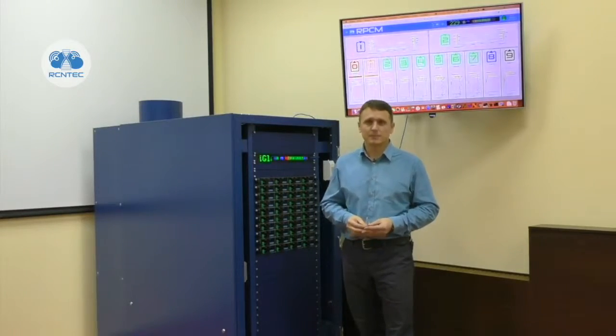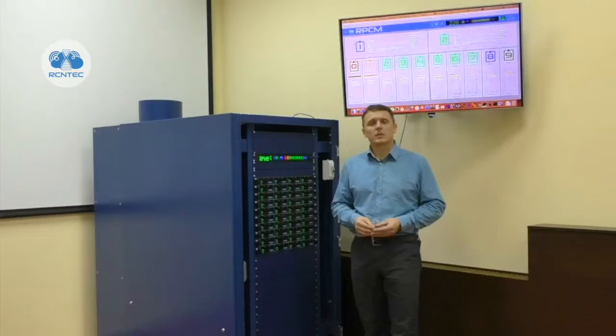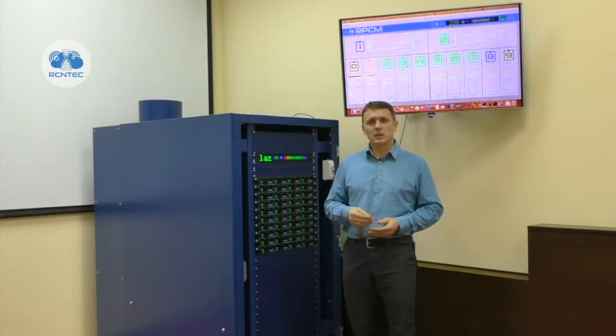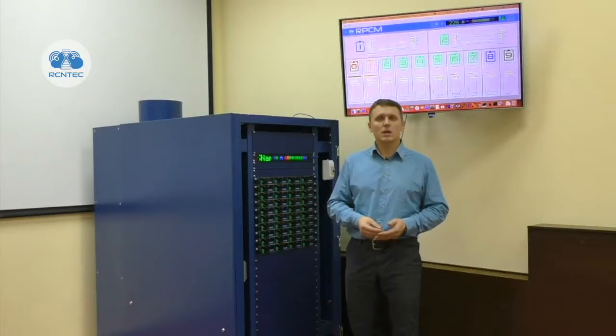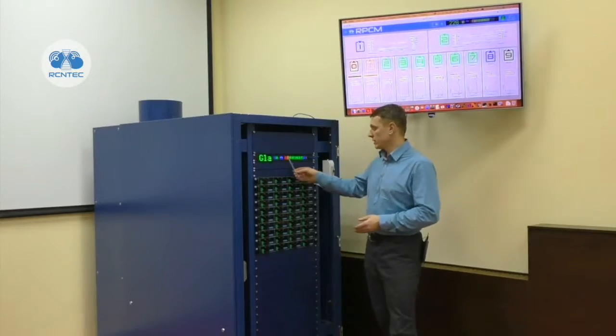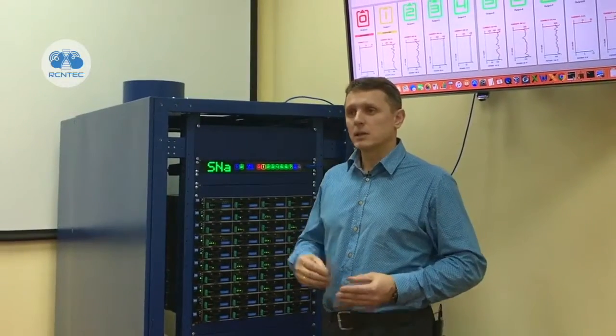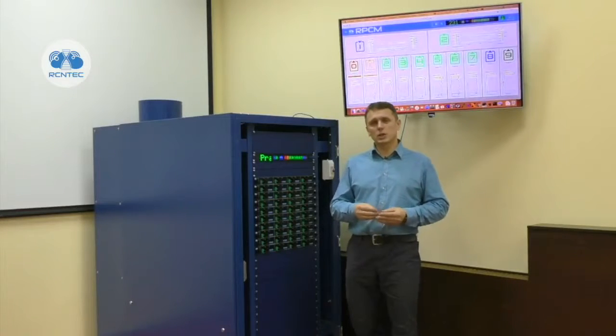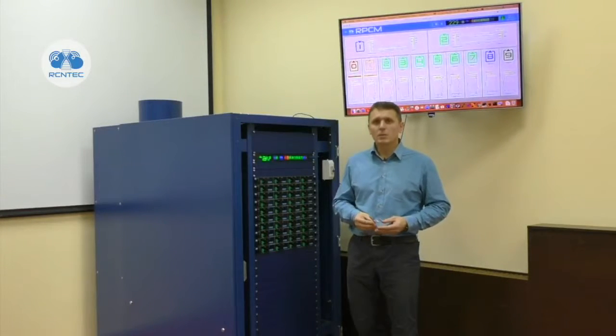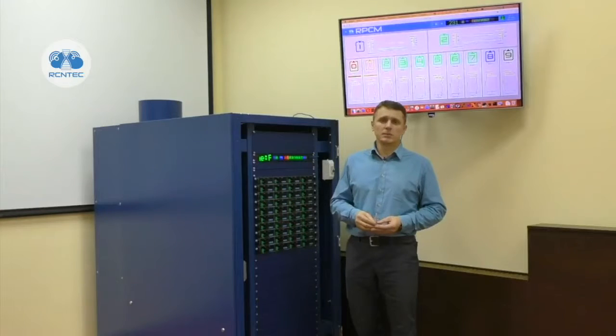In addition, RPCM has the capability to determine the existence of properly connected grounding, which increases operational safety and helps to prevent or troubleshoot equipment malfunctions. We have implemented the Smart Start feature with customizable activation sequence and delays for each outlet. It allows customers to start up infrastructure services correctly and eliminate high inrush currents during recovery from complete site power loss.